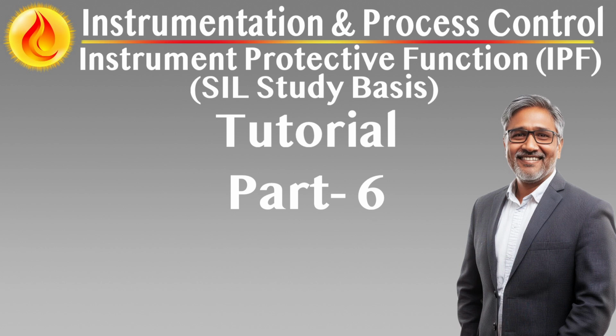Coordination and handover requirements. Shift handover awareness. Any active overrides must be explicitly communicated during shift handover with acknowledgement by incoming operators. Override logs should be integrated into shift reports and standing instructions. Cross-discipline communication. Operations, instrumentation, safety, and control system teams must maintain continuous coordination throughout the override period, especially if troubleshooting activities are underway.